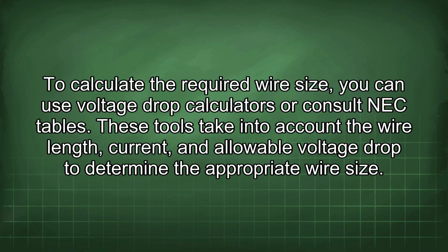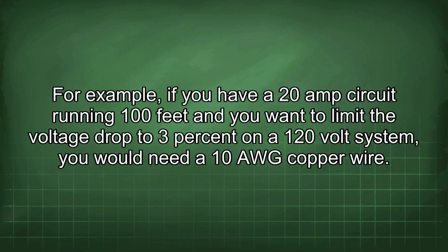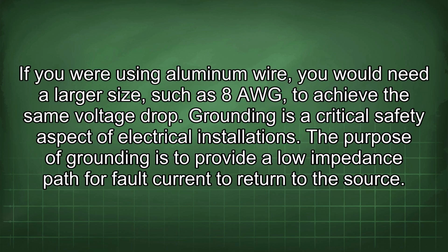To calculate the required wire size, you can use voltage drop calculators or consult NEC tables. These tools take into account the wire length, current, and allowable voltage drop to determine the appropriate wire size. For example, if you have a 20 amp circuit running 100 feet and you want to limit the voltage drop to 3% on a 120 volt system, you would need a 10 AWG copper wire. If you were using aluminum wire, you would need a larger size, such as 8 AWG, to achieve the same voltage drop. Grounding is a critical safety aspect of electrical installations.